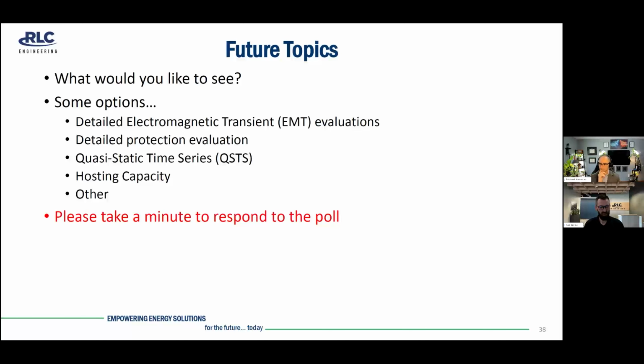Mike, feel free to jump in here as well, but for traditional studies, we're not often using QSTS. That's normally something we use for 8760 curtailment or our Volt-VAR operational studies, which I mentioned is part of our detailed design process. But we use CYME primarily, and the lowest you can get on that time step is 1 second. Sometimes we'll increase that for efficiency, as long as it's at least half of the fastest regulation device delay. So if an LTC has a 30-second tapping delay, then we'll simulate it at 15 seconds, for example.